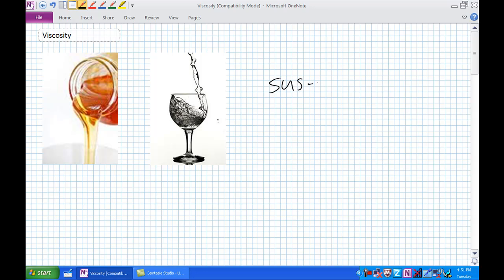It's called a SUS, Saybolt Universal Seconds. And the key there is the seconds. You know, honey would have a higher SUS rating because it takes a longer time to come out, okay? And that's how it's measured. It really is. I mean, you don't pour it over your head.